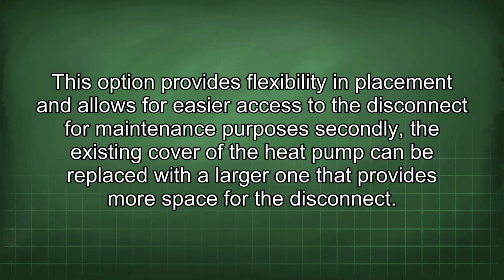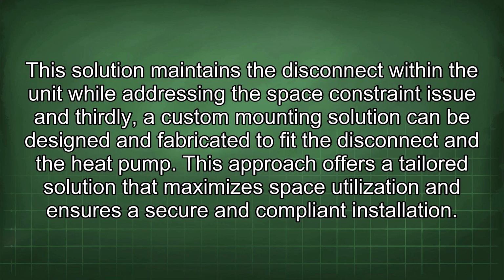Secondly, the existing cover of the heat pump can be replaced with a larger one that provides more space for the disconnect. This solution maintains the disconnect within the unit while addressing the space constraint issue. And thirdly, a custom mounting solution can be designed and fabricated to fit the disconnect and the heat pump. This approach offers a tailored solution that maximizes space utilization and ensures a secure and compliant installation.